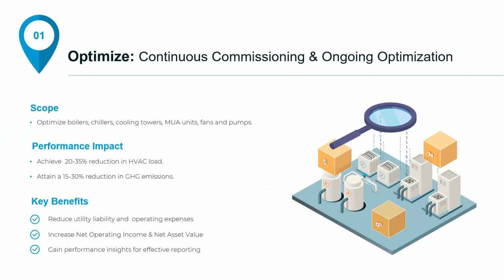So what is optimization, at least for most buildings, and certainly the buildings we're talking about in this case study today? It's really about taking the existing mechanical systems they have, primarily the boilers, chillers, cooling towers, makeup airs, fans, and pumps, and putting on smart controls that use best-in-class algorithms to get as much as possible out of the existing systems as installed in the building today. The reality is that most buildings, as advanced as we may think the controls are, whether multi-res, typical commercial, or institutional buildings, there's still a gap between what we can optimally do to deliver heating and cooling and optimize the mechanical plant versus what we're actually doing today.